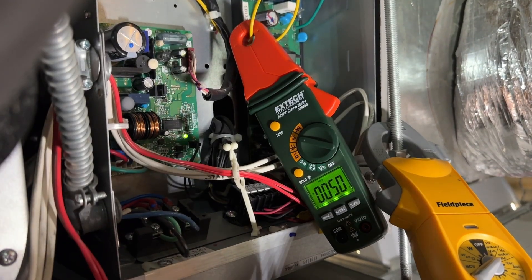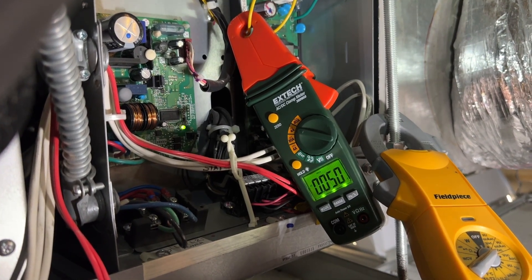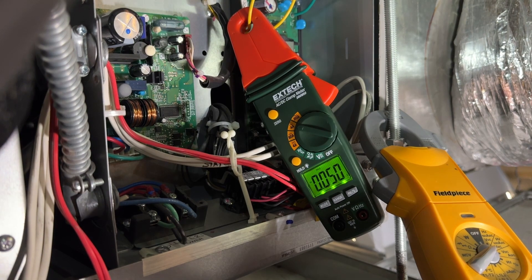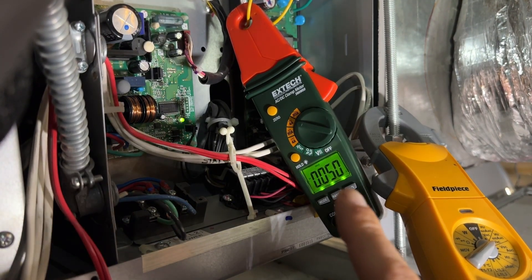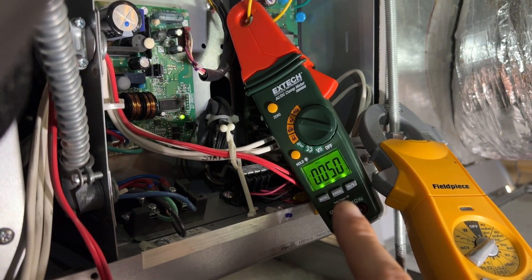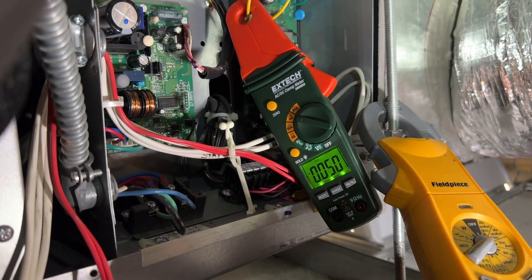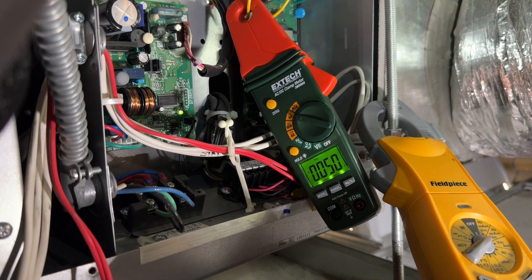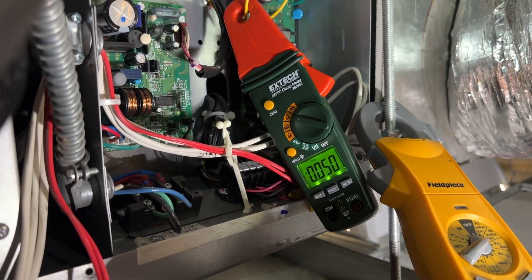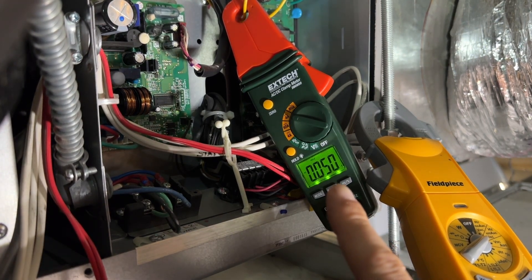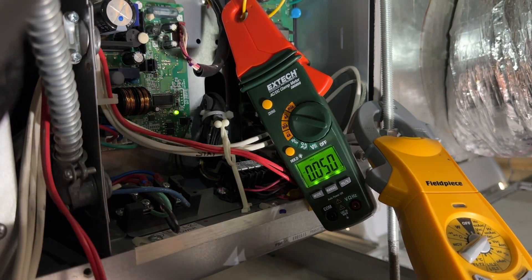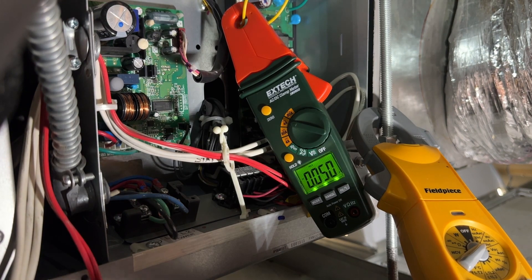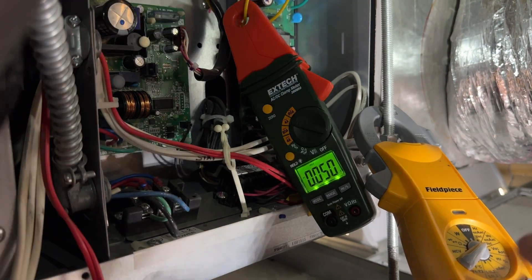So the pump is using that power now whether or not it's running whether it's locked up we don't know. Let me comment on this 50 milliamps here. You know when I said it may be running or it may be locked up typically you think when a motor is locked up it'll pull excessive amps and I'm pretty sure that it's not locked up but when you're dealing with something like a shaded pole motor locked rotor amps it can be really hard to tell the difference. I mean it is just not much so that's why I want to be careful about just assuming anything but I would expect to see something a bit higher than this if it was locked up.